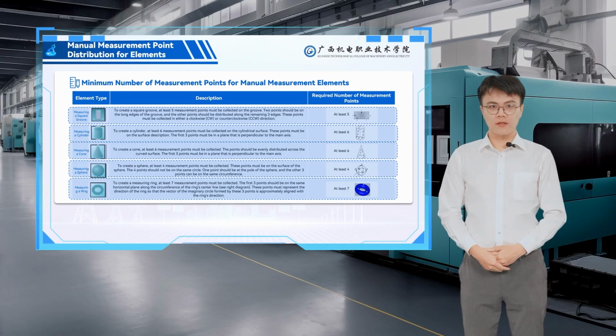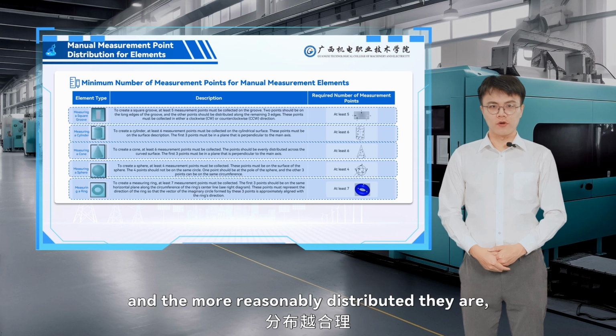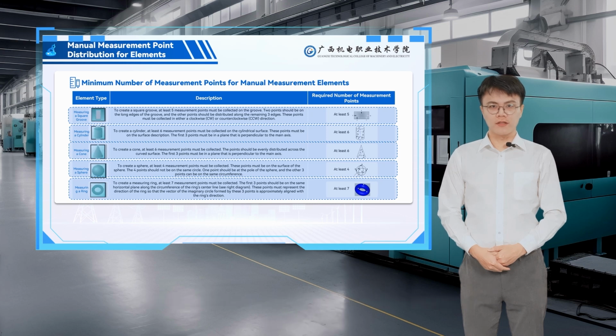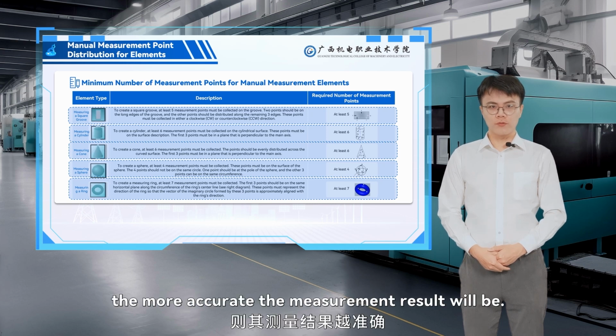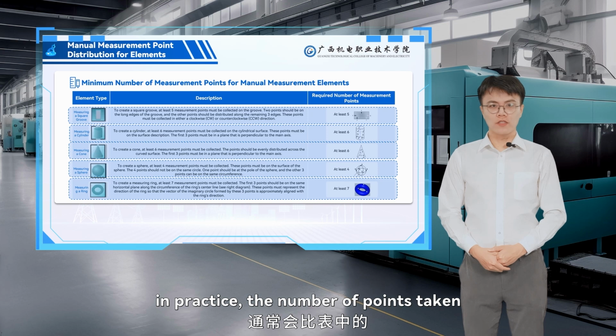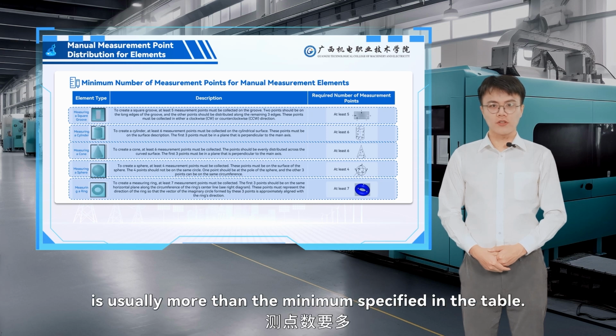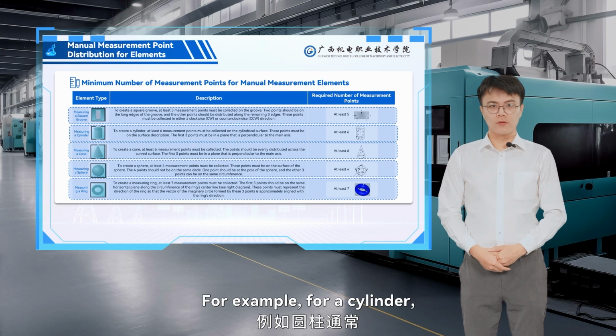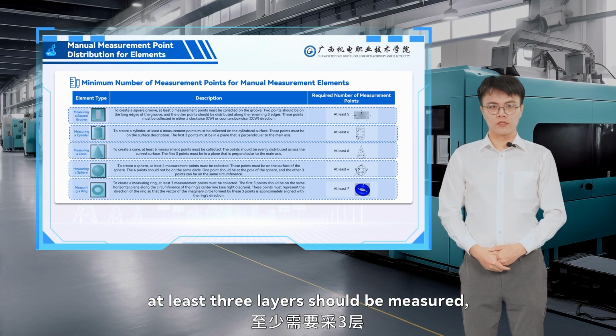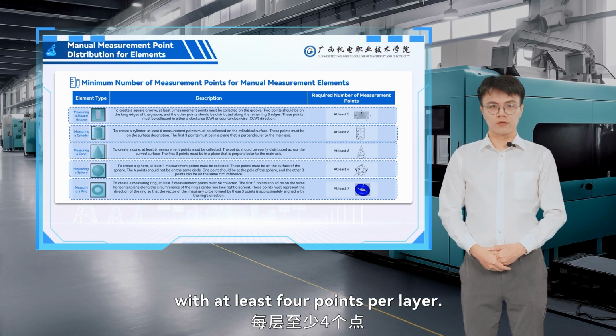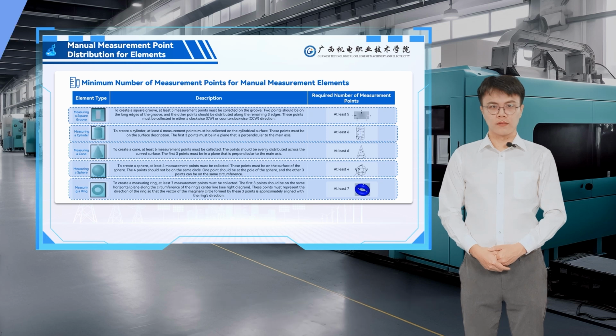When measuring, the more points are taken and the more reasonably distributed they are, the more accurate the measurement result will be. Therefore, in practice, the number of points taken is usually more than the minimum specified in the table. For example, for a cylinder, at least 3 layers should be measured, with at least 4 points per layer.